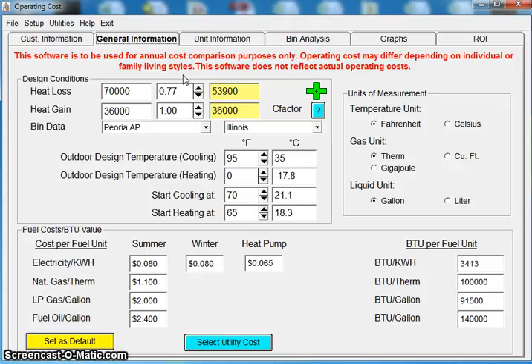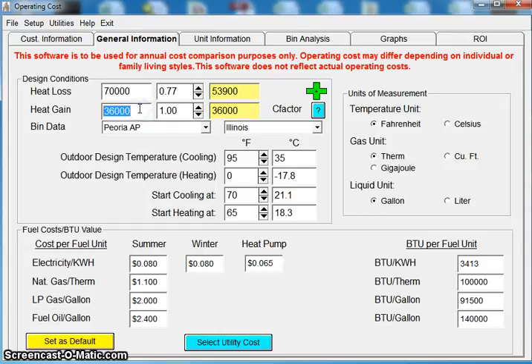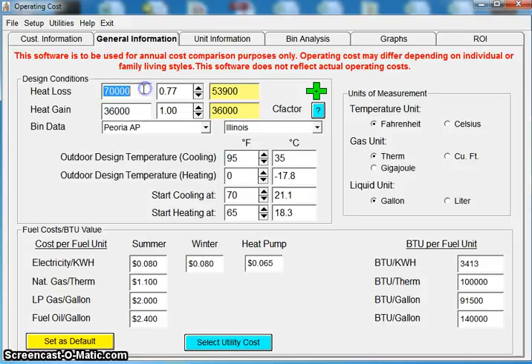What you have to worry about is step one, your heat loss and heat gain. If somebody currently has a 120,000 BTU furnace, we're not going to calculate their operating costs based on 120,000 BTUs. We're going to calculate it based on what you came up with in your load calc.